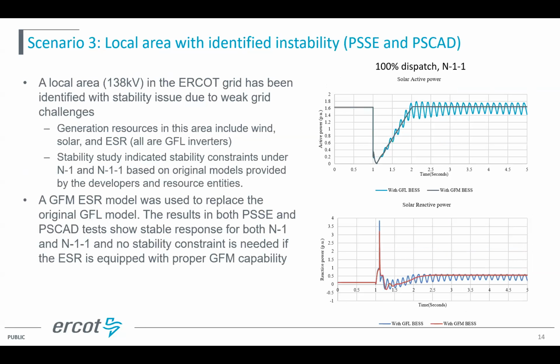The last scenario is a local area, a 138 kV area in Texas. It has been identified with stability issues. In this area we have wind, solar, and battery, and they are all grid following inverters. We ran dynamic simulation and found there are N-1 and N-1-1 instabilities based on the original model and the parameters provided to us. Then for the battery, we switched the model from the original grid following to grid forming, again respecting the maximum current capability. We performed the study in both PSSE and PSCAD, and found that the N-1 and N-1-1 issues both go away when we have grid forming models.